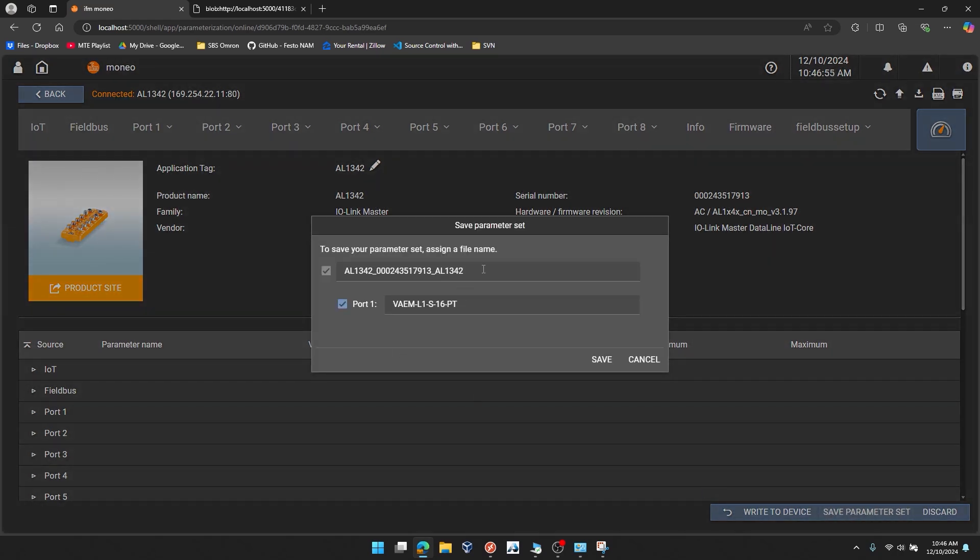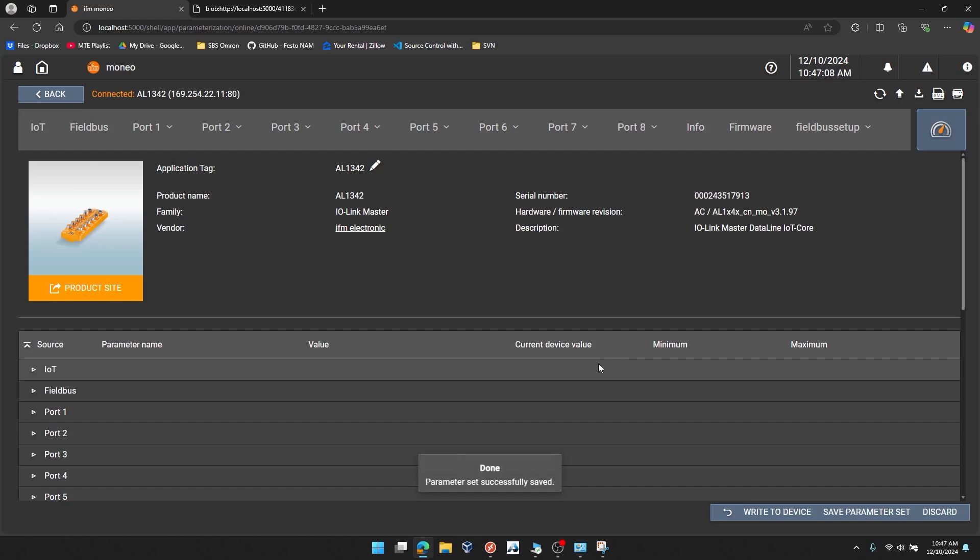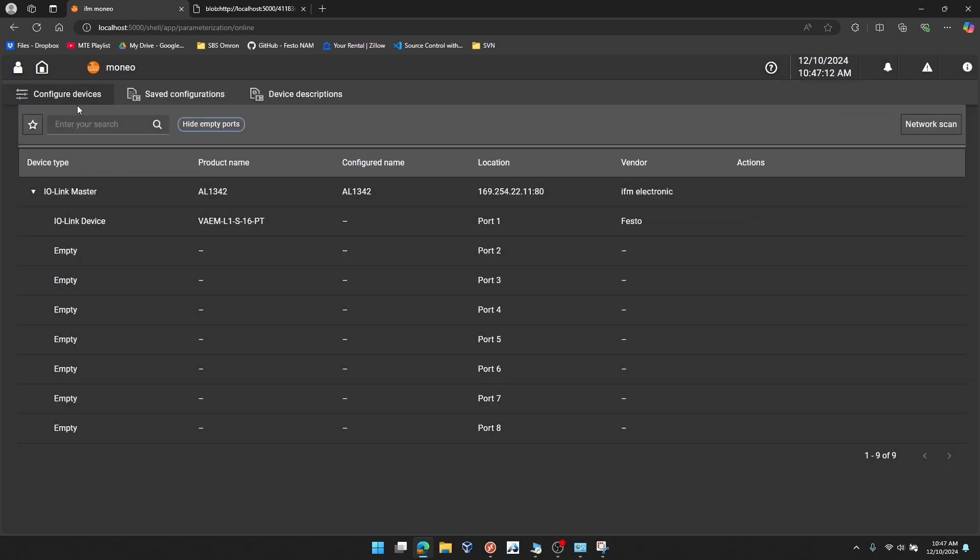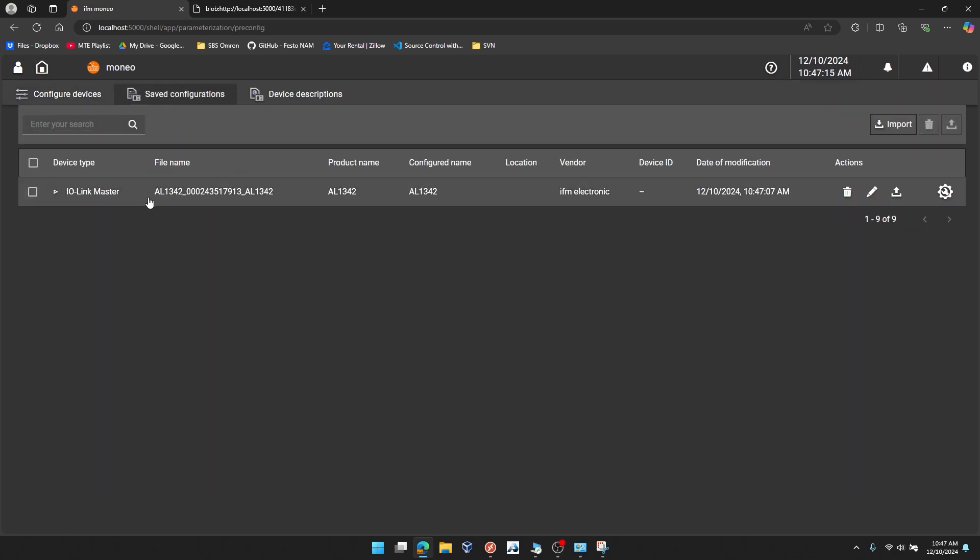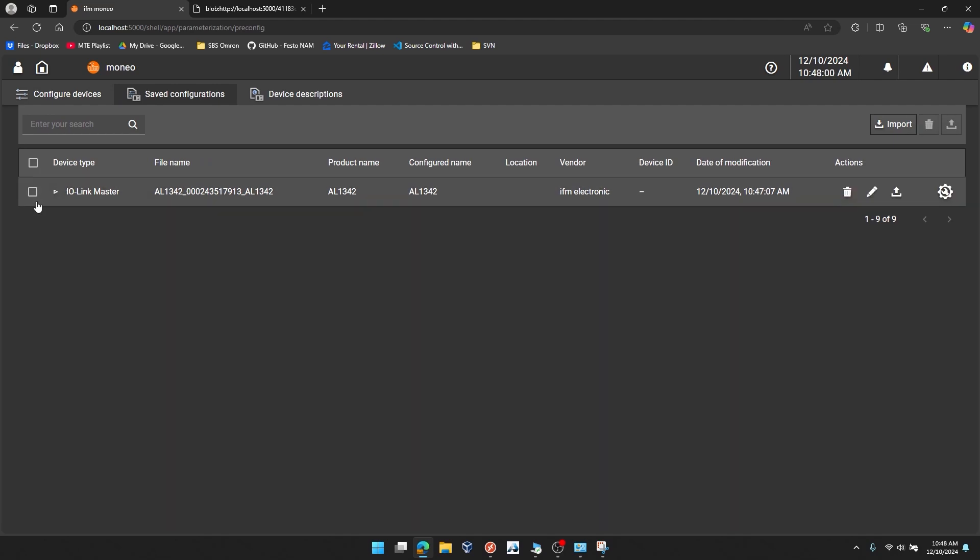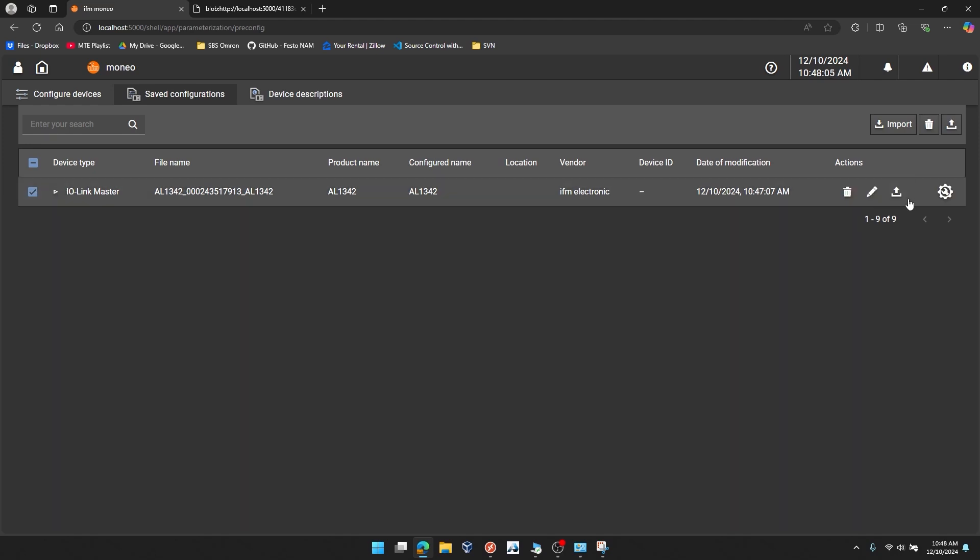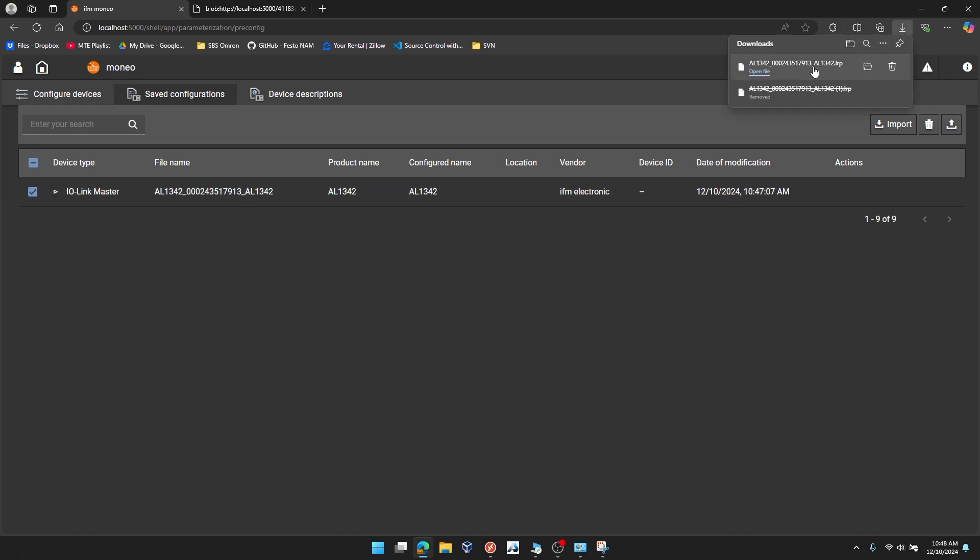And the next thing we'll do is we've successfully configured our IO-Link master for the parameters we're trying to set up today. And I want to save that parameter set for the IO-Link master. So in the bottom right corner, you'll see save parameter set. You can check the boxes for the master device that's defaulted and then the individual ports that you want to save. I've only configured settings for one port from the default, so it only gives me one option. So I'm going to click save. It says the parameter set was successfully saved. And you can confirm that if you go back and go to saved configurations. You can see here, this is the configuration that I just saved. Now, I'm going to check the box for that saved configuration, which does include all the port settings, like I mentioned. And I'm going to export there. That export, as you can see, is now in my downloads folder for my PC.